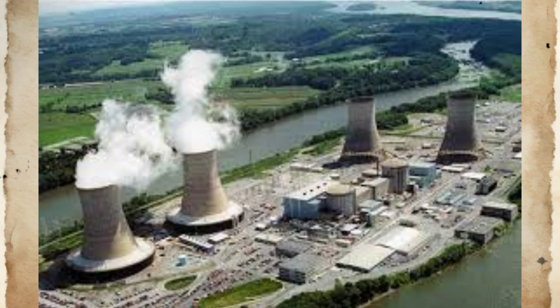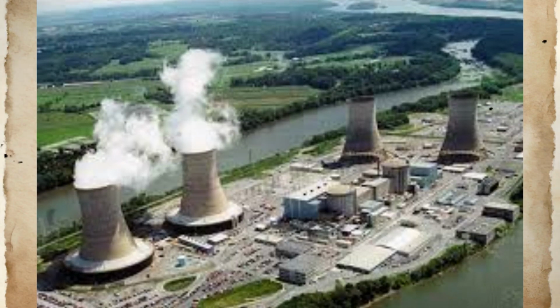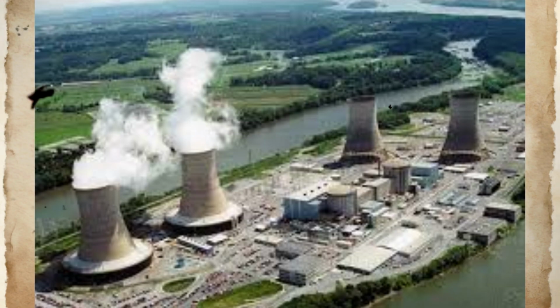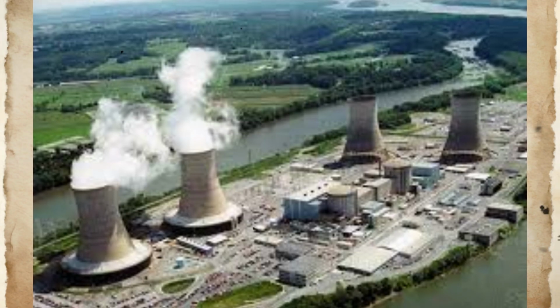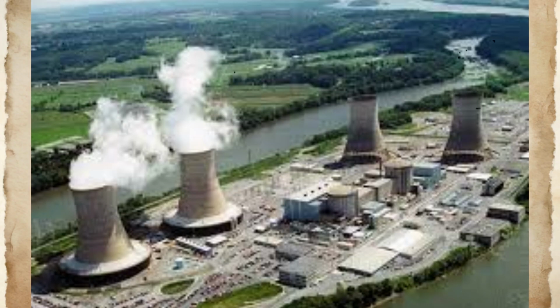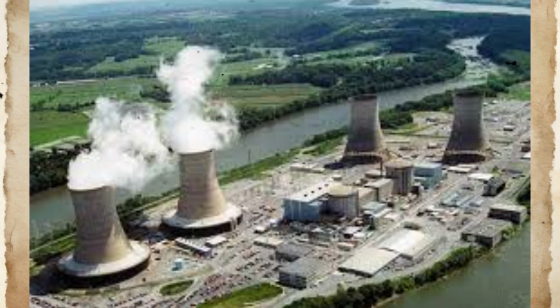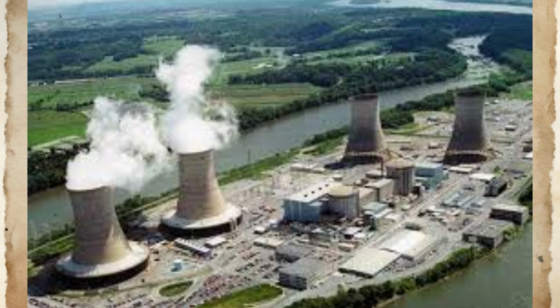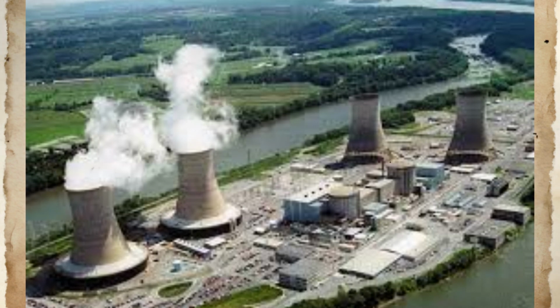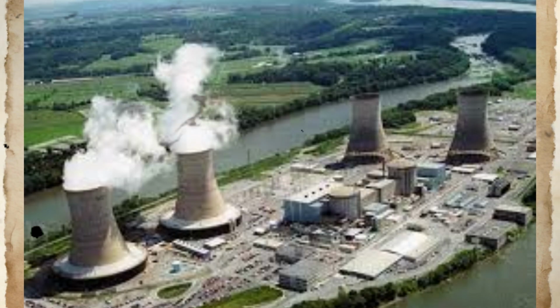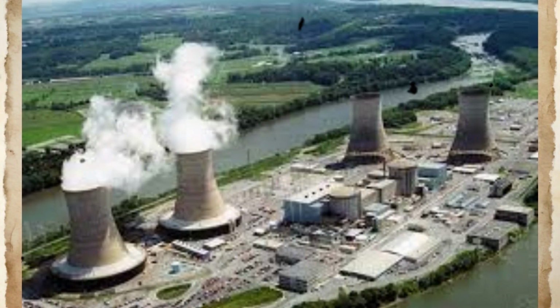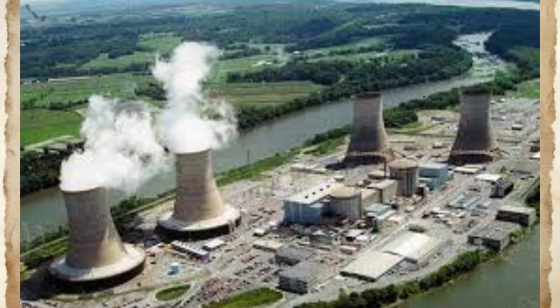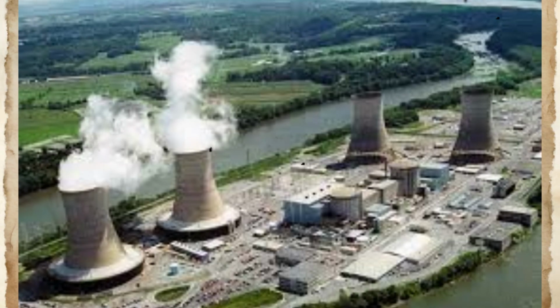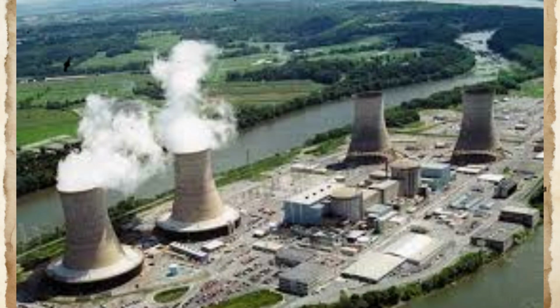as it accumulated. The reactor water level indication system provided misleading information throughout the core damage progression due to reference leg flashing caused by high containment temperatures. As containment atmosphere temperature rose above 100 degrees Celsius due to steam and energy released from core damage, water in the instrument reference legs began boiling, creating vapor bubbles that caused indicated water level to appear higher than actual water level within the reactor vessel. This instrumentation failure meant that operators received progressively less reliable information about core cooling adequacy, precisely when such information was most critical.